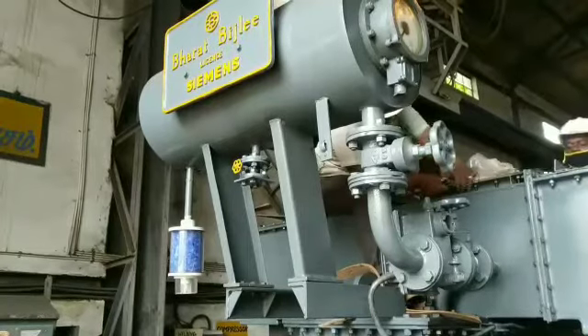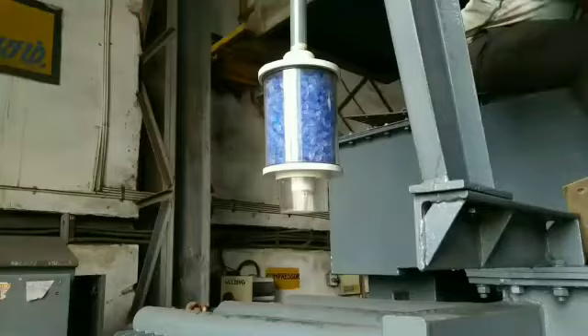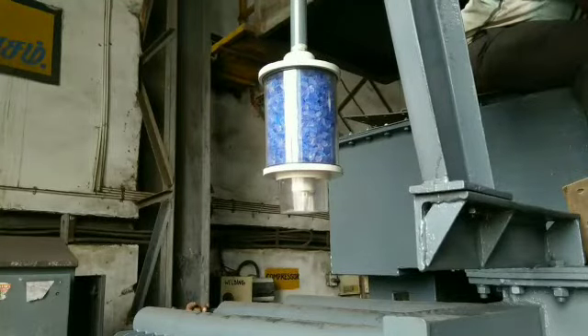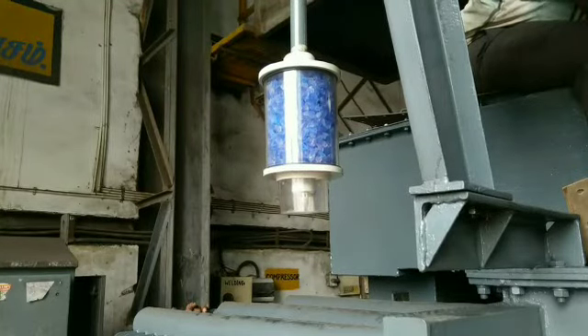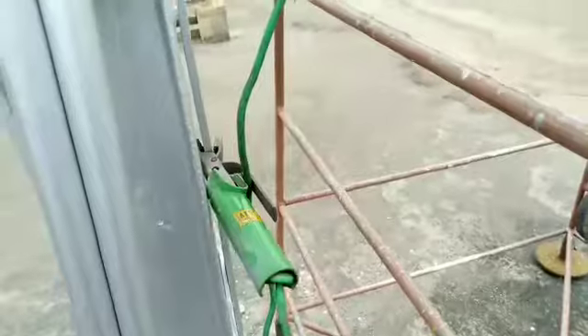In the transformer, the color of the silica gel should be blue, that is, it should be in good condition, and it should be inspected periodically. While working in a substation, an additional earth rod is connected for double isolation, that is, one inbuilt earth rod and an additional discharge rod.